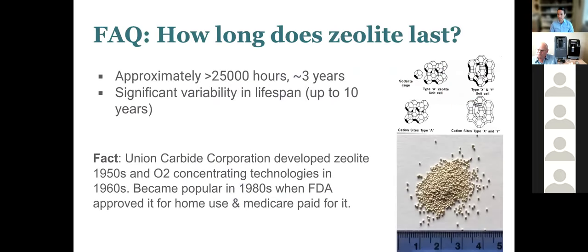Quick note on zeolite. A common question that comes up is, how long does the zeolite, this material in the sieve beds that filters, last? The short answer is it's highly variable and depends on how that unit was cared for and the operating environment. A good rule may be around 3 years, or 15 to 25,000 hours of continuous operation. This is going to vary, again, depending on how it's taken care of, the operating environment, and also the manufacturer's recommendations. Always check the service manual. There will be some mention of this in there.